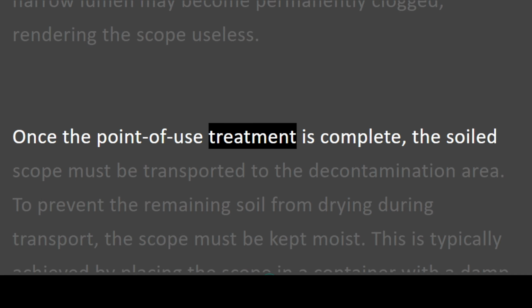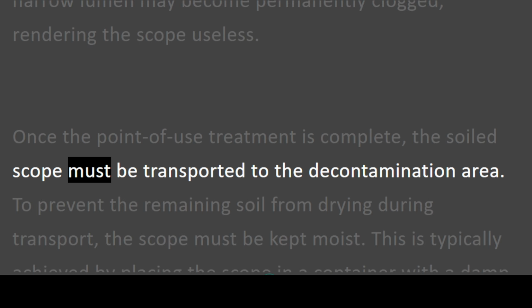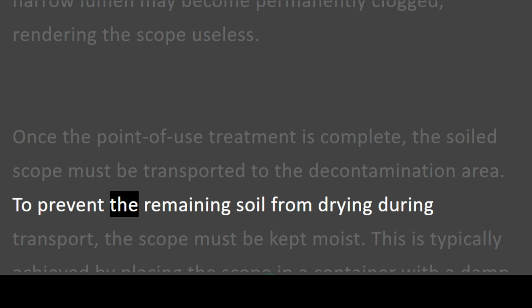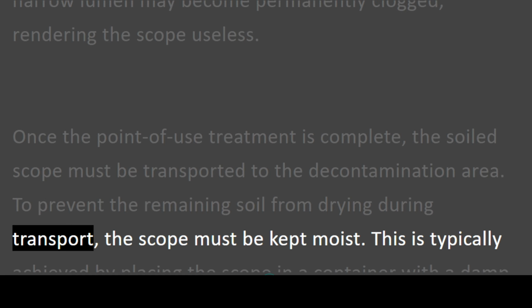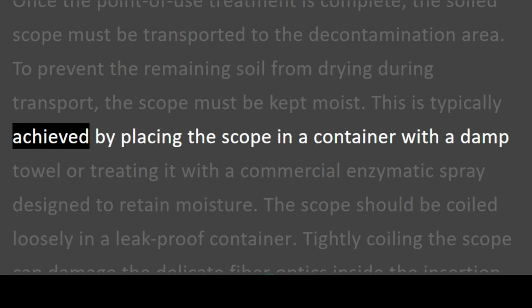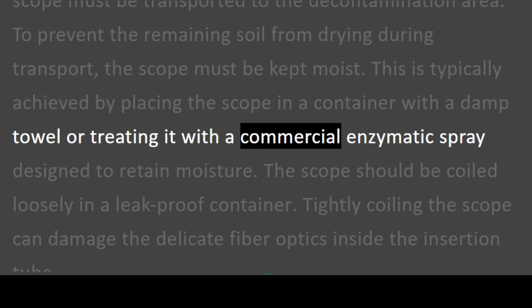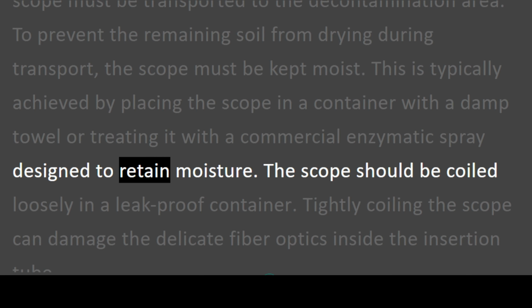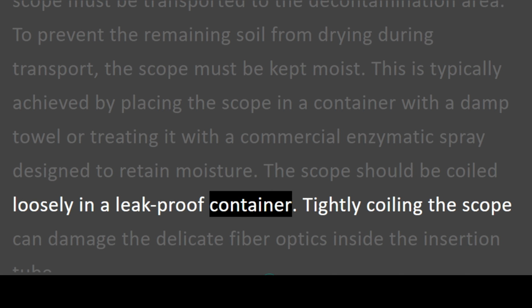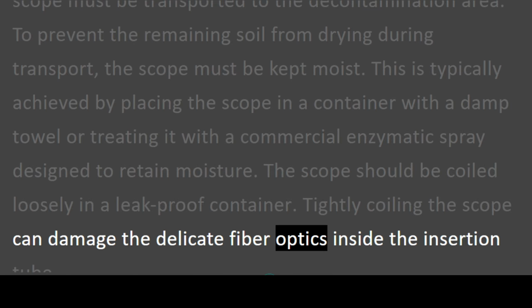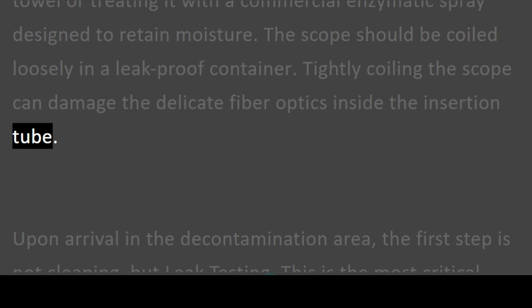Once the point-of-use treatment is complete, the soiled scope must be transported to the decontamination area. To prevent the remaining soil from drying during transport, the scope must be kept moist. This is typically achieved by placing the scope in a container with a damp towel or treating it with a commercial enzymatic spray designed to retain moisture. The scope should be coiled loosely in a leak-proof container. Tightly coiling the scope can damage the delicate fiber optics inside the insertion tube.